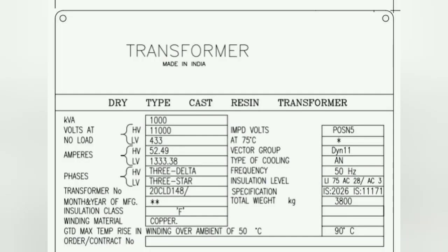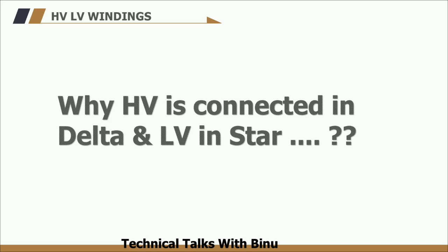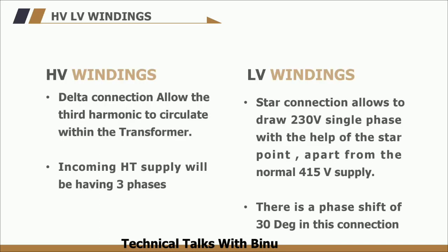Now coming back to the nameplate details, we are going to see the winding details. The HT windings are connected in delta and the LT windings are connected in star, and both windings are 3-phase. The delta winding on the HT side allows the third harmonic current to circulate within the transformer and prevents harmonics from going out into the system. Also, the HT supply runs on a 3-phase 11 kV system with no neutral or earth point, so a star point is not required. The secondary is wound in star, giving an output of 433 V between lines and a domestic supply voltage of 240 V between line and neutral. There is a phase shift of 30 degrees between the primary and secondary voltages.